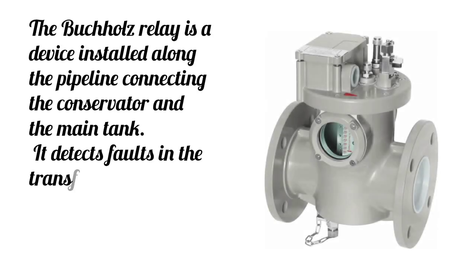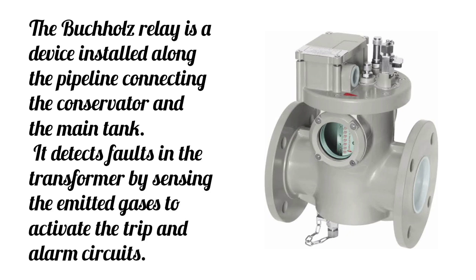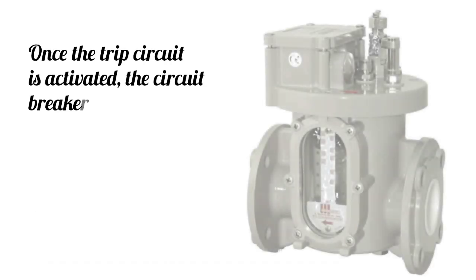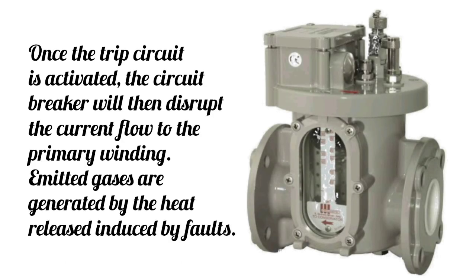The Buchholz relay is a device installed along the pipeline connecting the conservator and the main tank. It detects faults in the transformer by sensing the emitted gases to activate the trip and alarm circuits. Once the trip circuit is activated, the circuit breaker will then disrupt the current flow to the primary winding. Emitted gases are generated by the heat released, induced by faults.